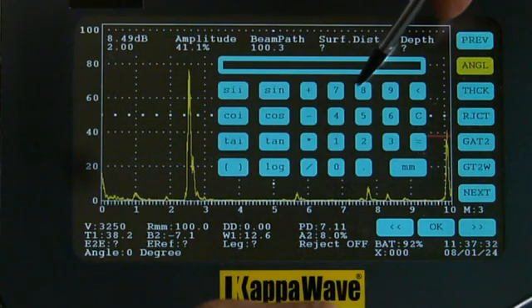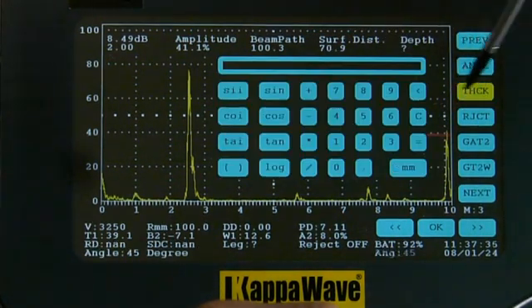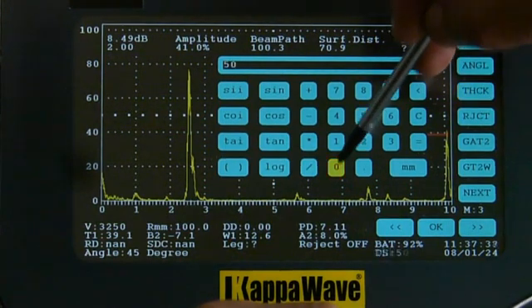We will now enter the angle of the probe, 45 degrees, and the thickness is 50mm because this is the thickness of the DAC block.